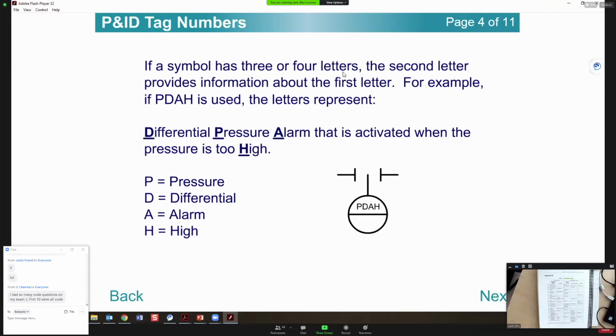If a symbol has 3 or 4 letters, the second letter usually provides information about the first letter. So in here, they give you an example. They call it the PDAH. P is for pressure, D is differential pressure, and A is the alarm. H means the pressure is too high. And usually the second letter, they call it the modifier of the first letter. That's what they call them in your book.